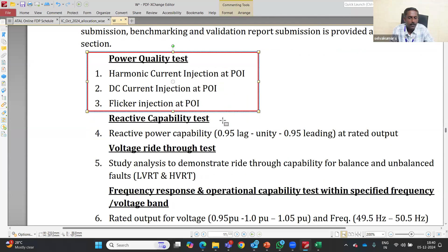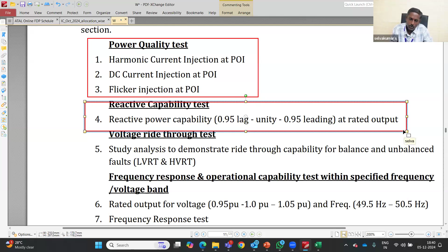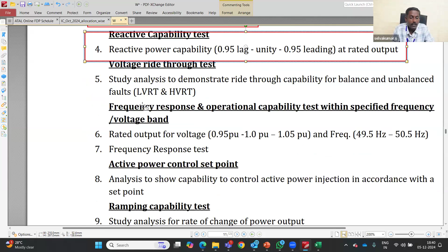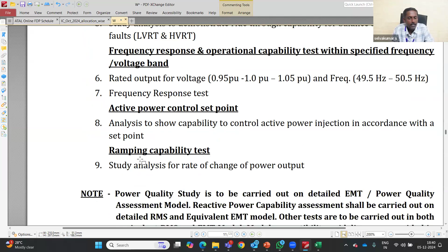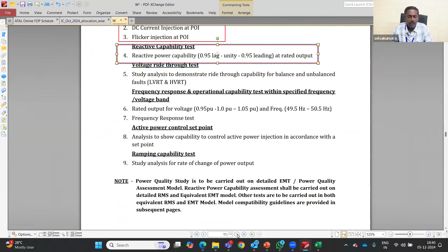Let me go to the next point - reactive power capability test. This is how much reactive power the wind turbine generators, solar inverters, or battery energy storage systems should meet. Voltage ride through - high voltage ride through, low voltage ride through. Frequency response - if the frequency is changing in the grid, how the wind turbine generator or solar inverter has to behave. Active power control set point. Ramping capability test.